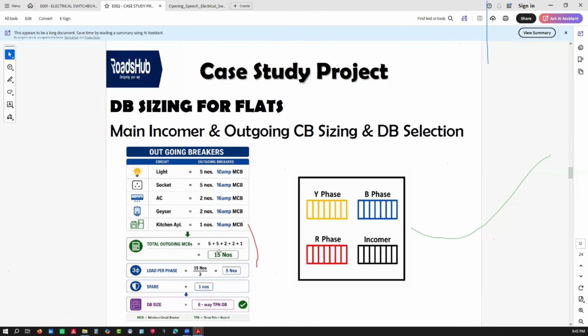Here, I need to divide by 3. Why? Because I have 3 phases. So if I'm tapping single phases from each phase, I need to know how many 3-phase circuits I have. So I have 5 3-phase circuits, but I have 15 single pole breakers that I'm using in that DB. So automatically, what is the DB that you're going to buy in the market? It will be a 6-way TPN DB.